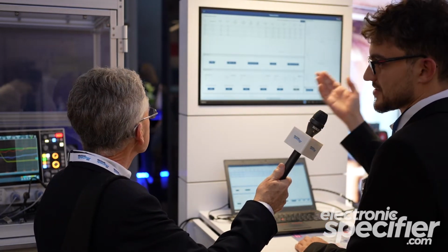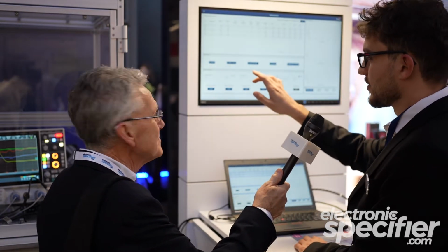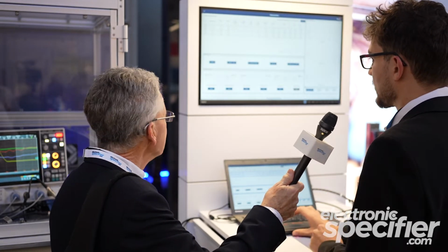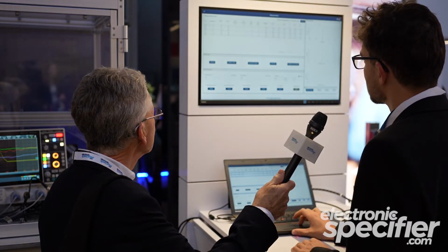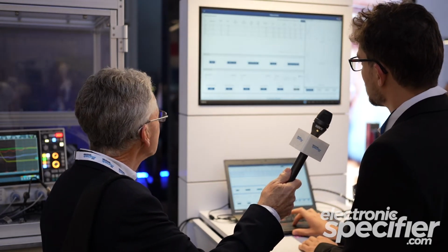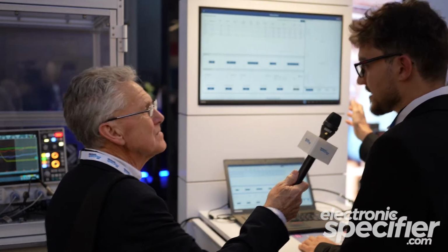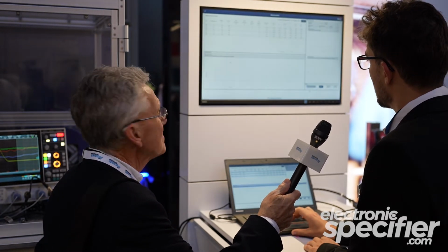We can sweep over temperature, DC voltage, current, and also your gate driver characteristics. That means the gate driver voltage and the gate driver on and off resistances. That can all be set from the software and swept over. For now, we're just going to test at 700 volts and at different currents. For simplicity, we're going to do a very simple sweep from 200 to 600 amps in 100 amp steps at 700 volts. Once we've defined these test parameters, I can actually start the test.